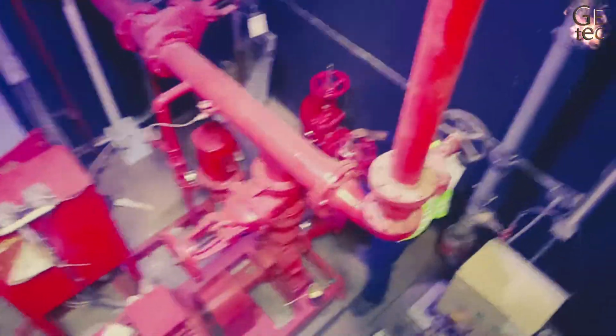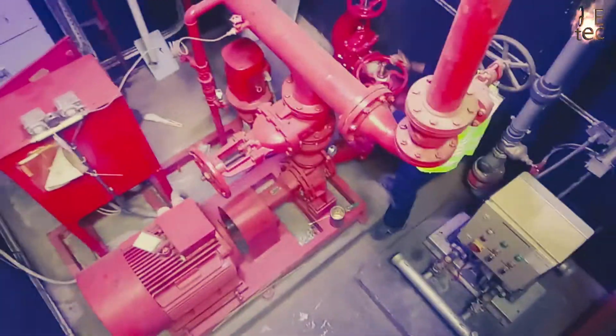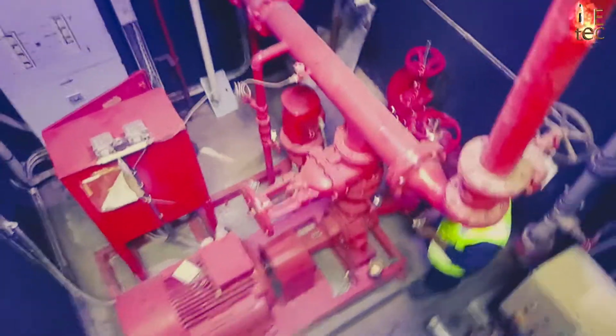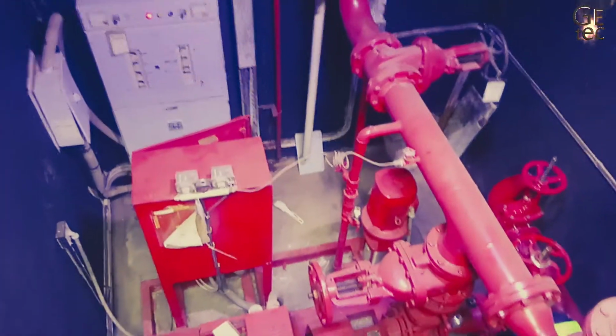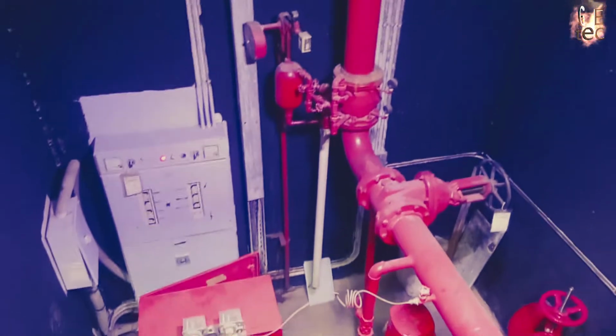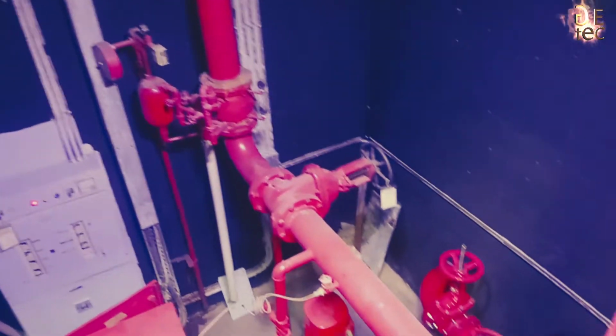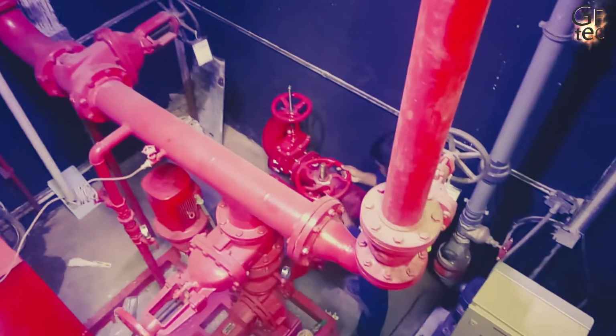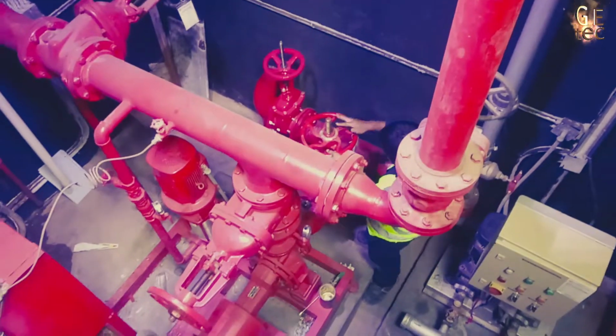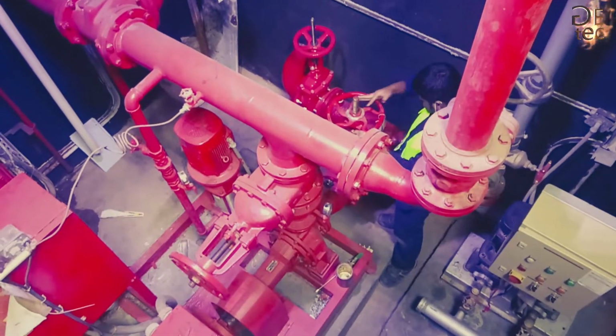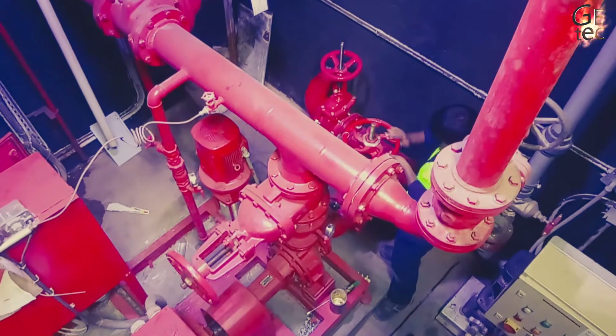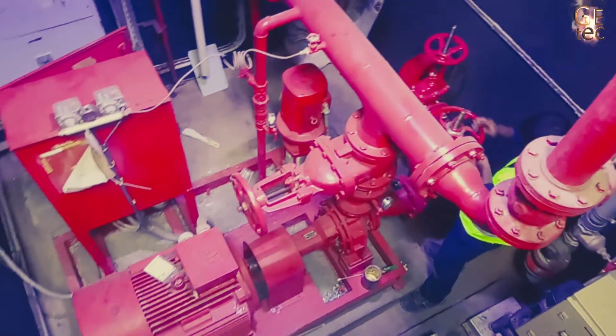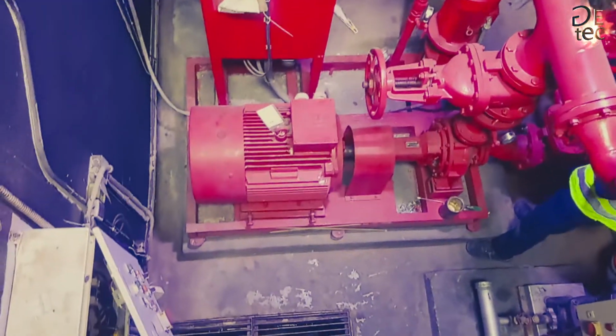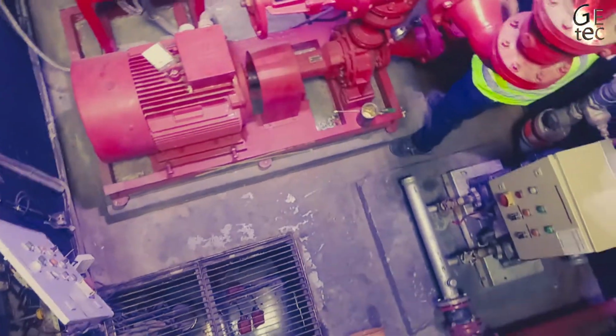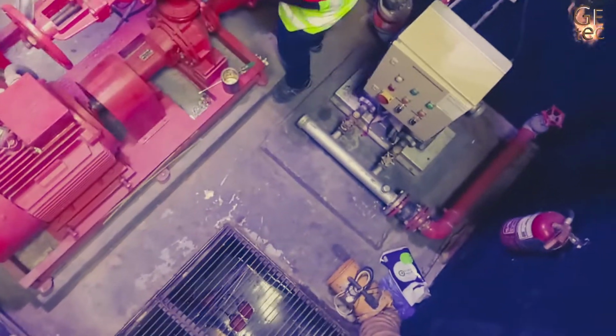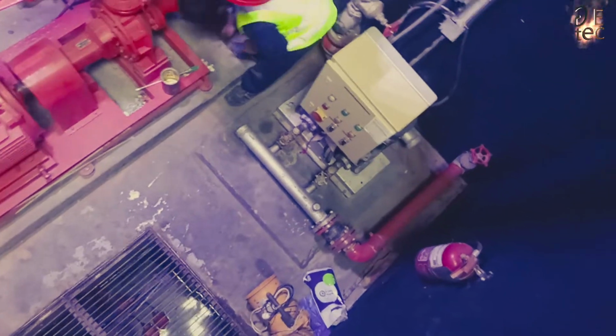A fire pump is a part of a fire sprinkler system's water supply and powered by electric, diesel or steam. The pump intake is either connected to the public underground water supply piping, or a static water source, for example, tank, reservoir, lake. The pump provides water flow at a higher pressure to the sprinkler system risers and hose standpipes. A fire pump is tested and listed for its use specifically for fire service by a third-party testing and listing agency, such as UL or FM Global.